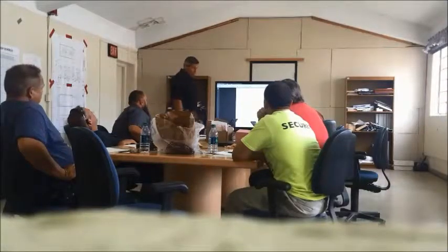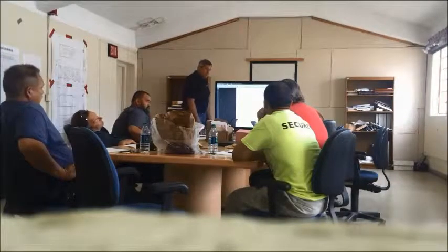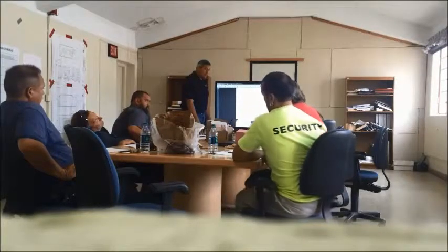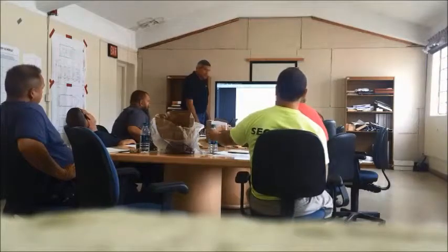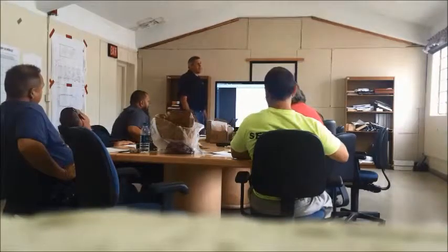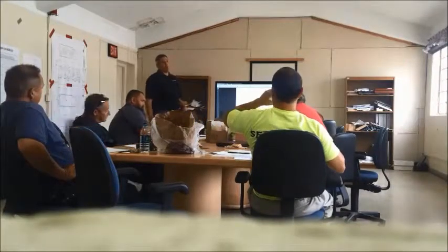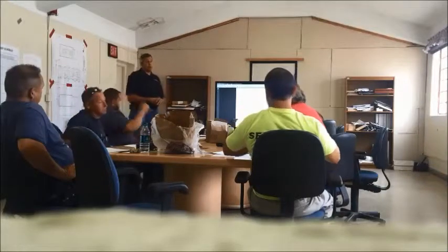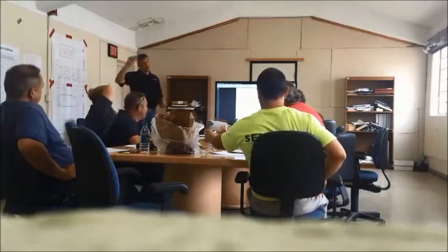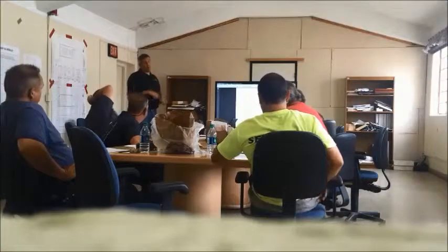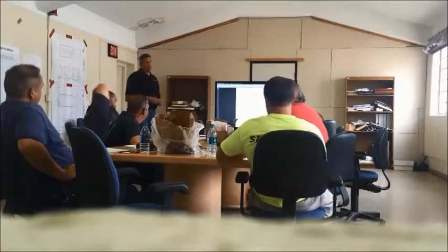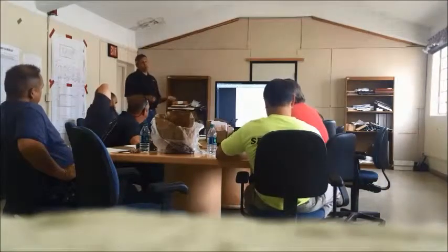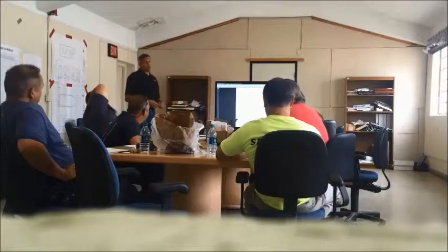Does each fume hood valve have its own little processor, controller? That's correct. Phoenix, because of the critical lab requirements, has their own control. They develop their own curves. There's like 64 points on a curve per valve to maintain the integrity when the hood goes open or closed. And they're fast reacting. The actuators from fully open to fully closed take about 15 seconds.